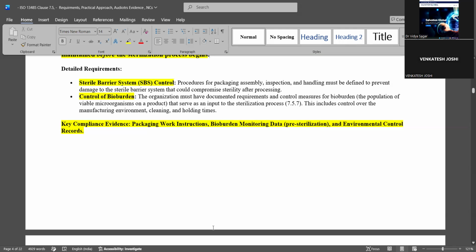You keep it in different parts of the clean room. You keep it at the machines, at the pass box, at the doors, and at the HVAC inlet units. And the other way is to do air sampling. In the settle plate method, the organisms settle on the petri plate. Air sampling is where you have equipment called air samplers. You pick up some volume of air, and that air is flushed on the petri plate with the media. So you will also know how much bioburden or microorganisms are in the air, and also on the floor by the settle plate method.